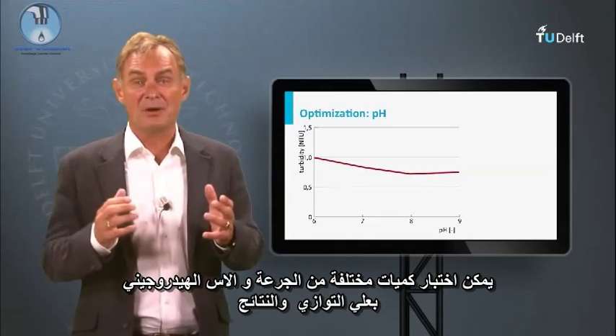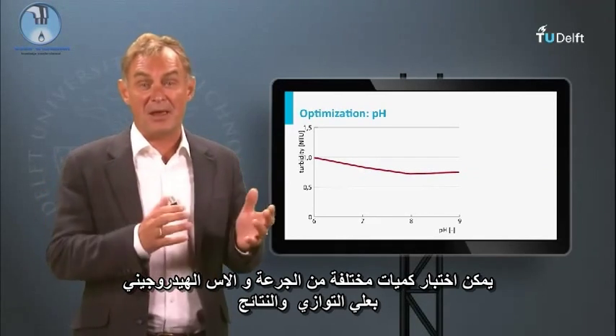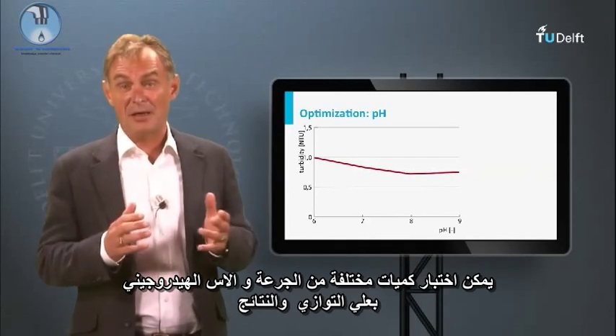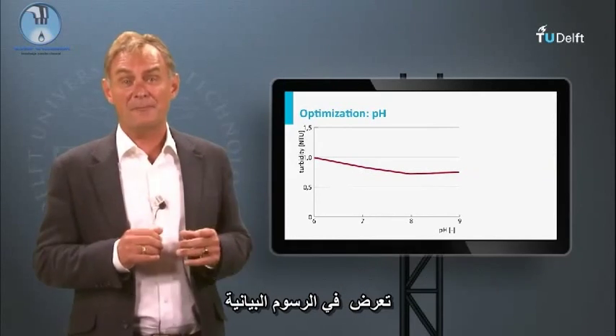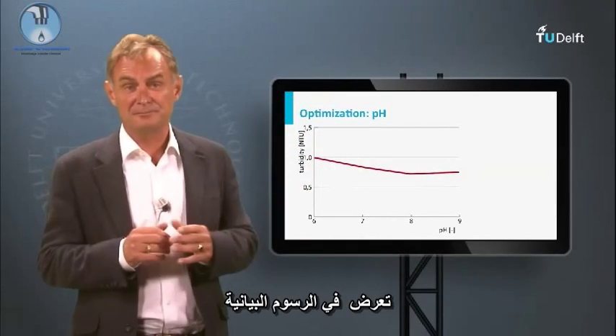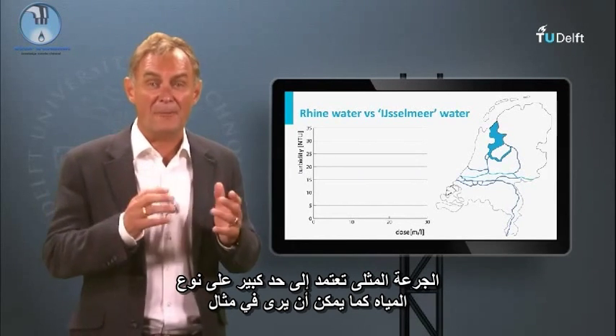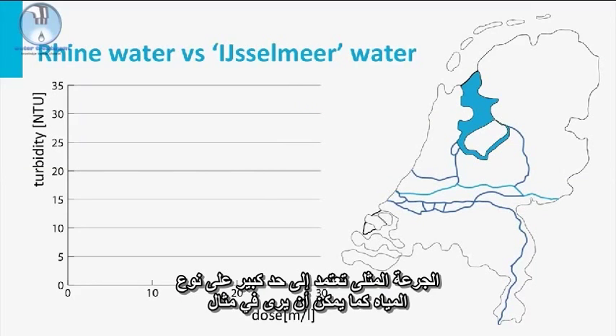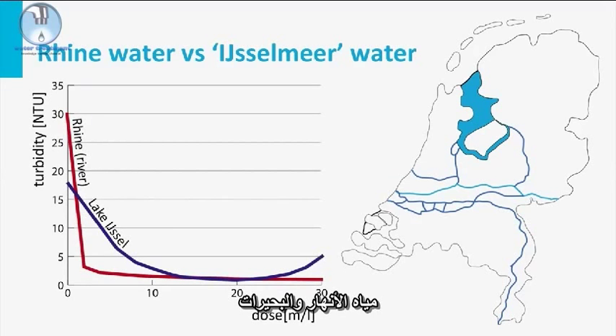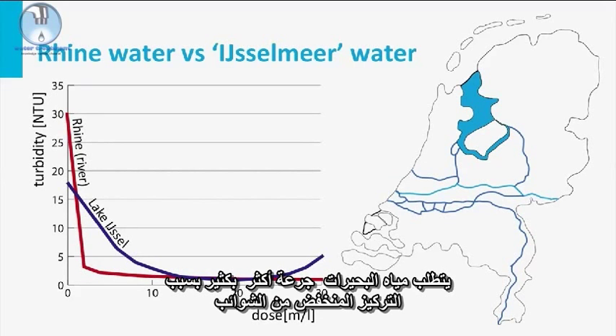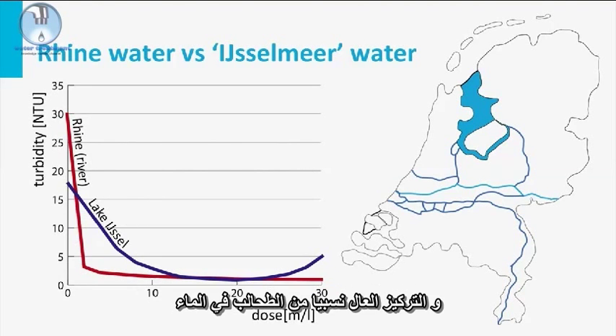The different combinations of dosage and pH can be tested in parallel and the results are presented in graphs. Optimal dosage highly depends on the type of water, as can be seen in the example of river and lake water. Lake water requires much more dosage because of the low concentration of inert material and the relatively high concentration of algae in the water.